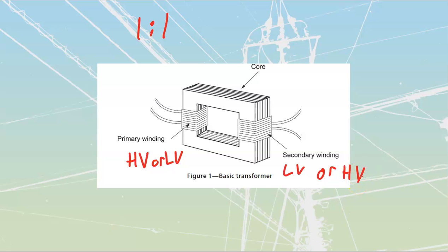Meaning that I can use this transformer, it's nothing more than a tool, to convert down from a value of voltage. I could come from a high voltage in to a low voltage out. That would be a step down type of application. Or alternatively, I could go from a low voltage in to a high voltage out. That would be a step up type of application. Primary does not refer to the voltage class. It just refers to the side that we are feeding the power in from. Secondary refers to the side that we are feeding to our loads.